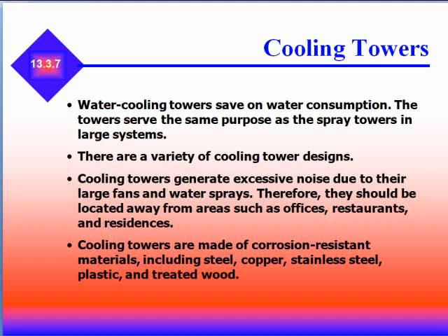Cooling towers are also a water-based system that save on water consumption, serving the same purpose as spray towers in larger systems. There are a variety of cooling tower designs. Cooling towers generate excessive noise due to their large fans and water spray, so they should be located away from offices, restaurants, and residences. Cooling towers are made of corrosion-resistant materials including steel, copper, stainless steel, plastic, and treated wood.